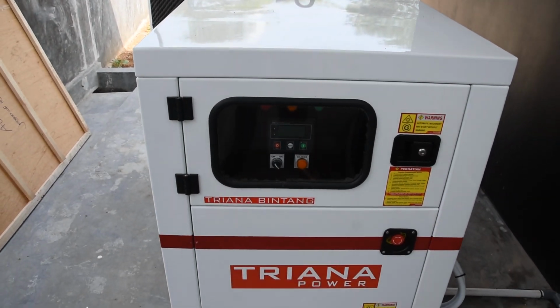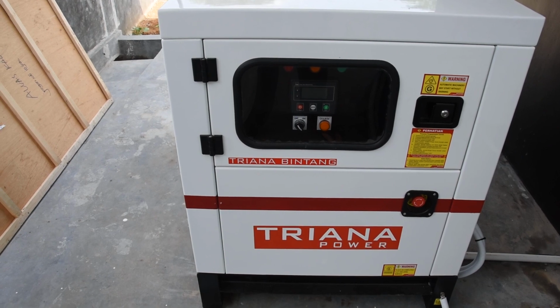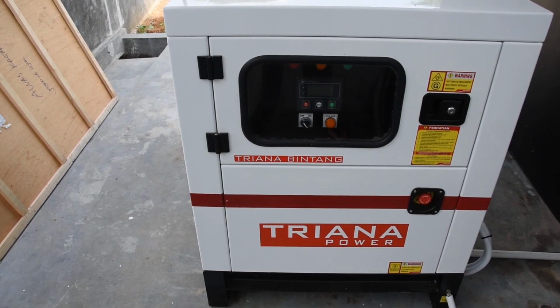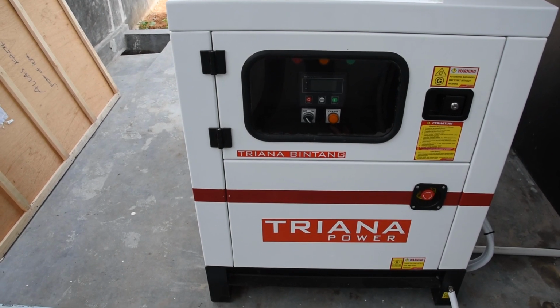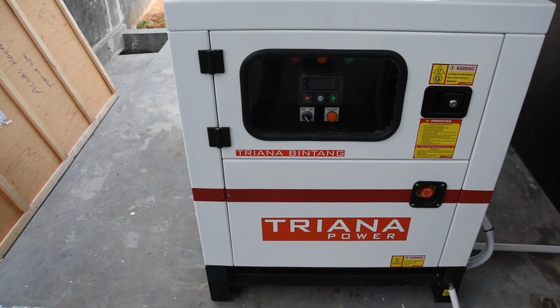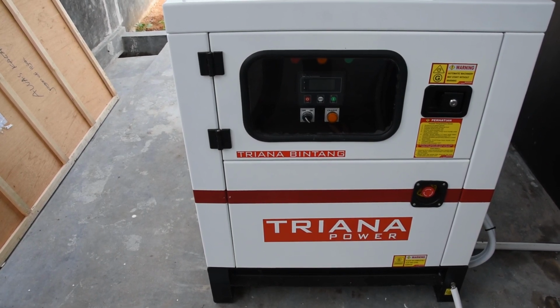Well, we have some teething troubles with the new setup. Both configurations are acting up. So the house configuration overnight was saying, give me all my power from the alternate source rather than using local battery, and we'll charge up the battery, which it shouldn't be doing. And over at the shed here, he was saying, I want to run the generator. Doesn't matter that I've got more than 60% charge in the batteries, I want to run the generator anyway and charge up the batteries.